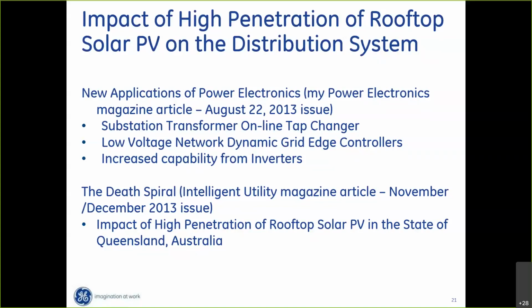You should see the voltage waveforms on that feeder when all of a sudden 35% of the homes start generating because the fog had gone away and now all these PV panels see the sun. The voltage literally spiked tremendously and then oscillated as clouds would go between the sun and the PV panels. The volatility of the voltage and reactive power on that feeder was unbelievable. I'd never seen anything like it before.